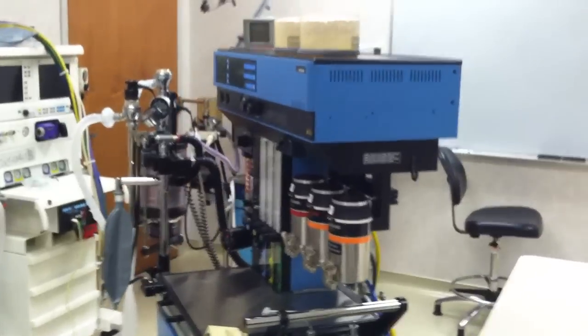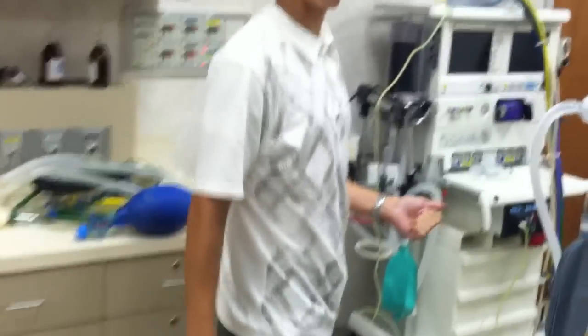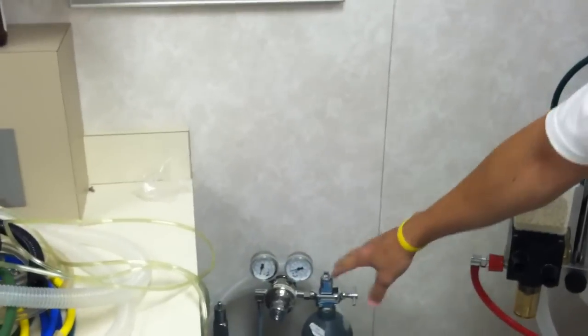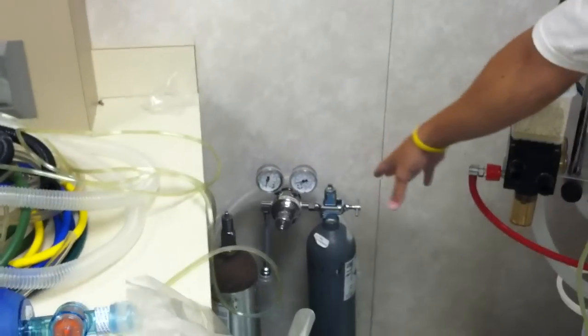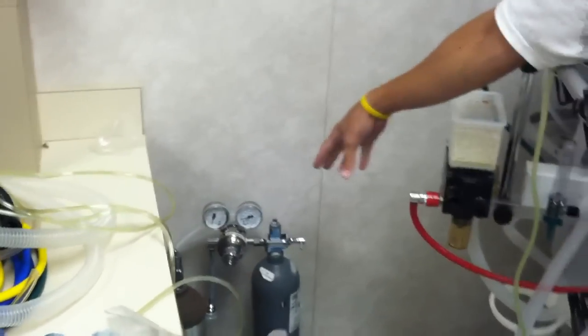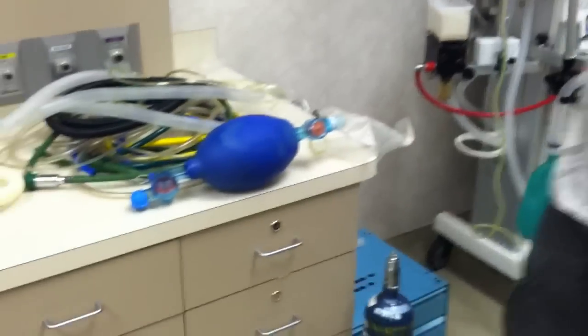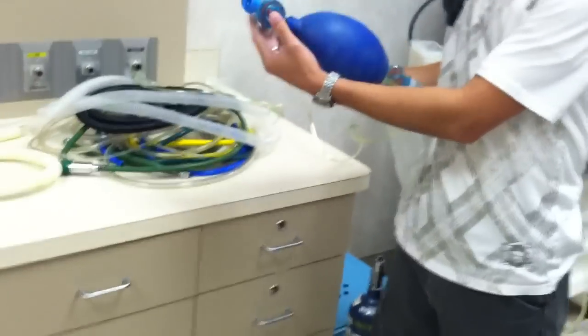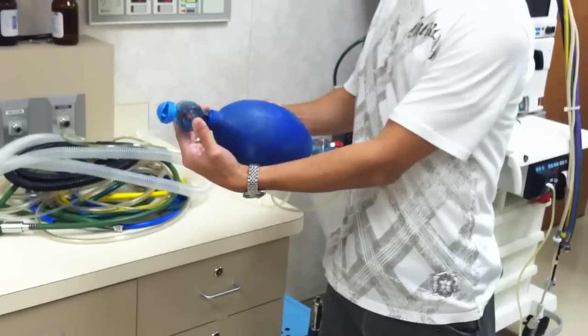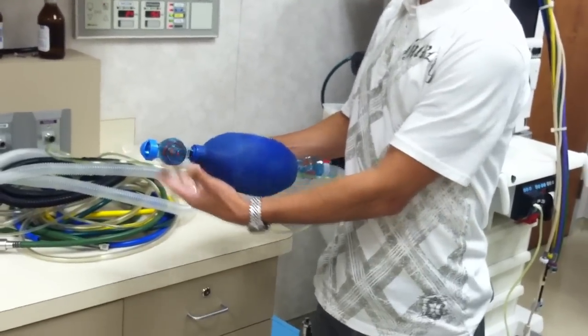Hey guys, we're gonna go over machine checkout now for the Narkomed. The first thing you want to do with any machine checkout is check your backup E-cylinder to make sure that it has oxygen. This of course isn't an oxygen tank, but you would want to make sure that your E-cylinder, your backup cylinder, had 1,000 psi minimum. You're going to go ahead and check your ambu bag, make sure it can hold positive pressure and that it can bring in air.